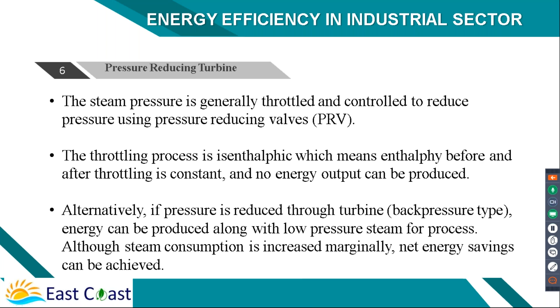Generally in any process industry, the boiler will generate steam at around 10 kg. But if you go to any end user equipment, there will be a pressure reducing valve, PRV, so the pressure is reduced to about 3 to 4 bar, and then it's given for the process, mostly for heating purpose. This 10 to 3 bar pressure reduction through a valve does not produce any useful work. So instead, because of technology development, we now have smaller steam turbines.